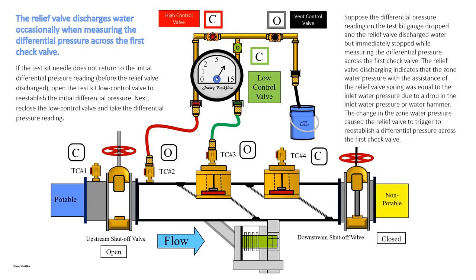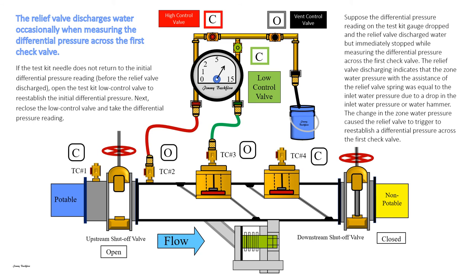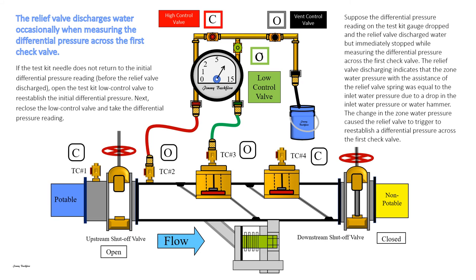The relief valve discharges water occasionally when measuring the differential pressure across the first check valve. Suppose the differential pressure reading on the test kit gauge dropped and the relief valve discharged water but immediately stopped while measuring the differential pressure. The relief valve discharging indicates that the zone water pressure, with the assistance of the relief valve spring, was equal to the inlet water pressure due to a drop in inlet water pressure or water hammer. The change in zone water pressure caused the relief valve to trigger to re-establish a differential pressure across the first check valve. If the test kit needle does not return to the initial differential pressure reading before the relief valve discharged, open the test kit low-control valve to re-establish the initial differential pressure. Then re-close the low-control valve and take the differential pressure reading.